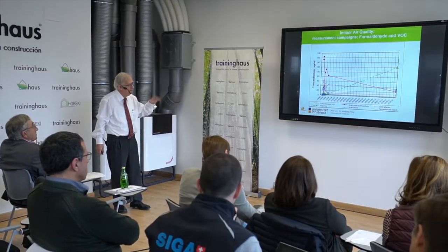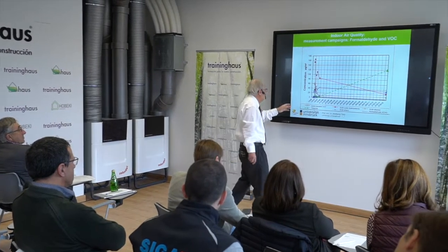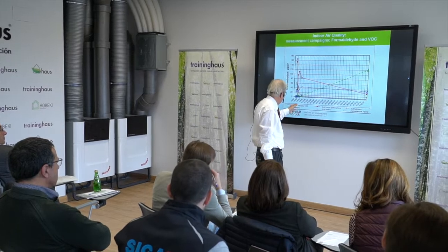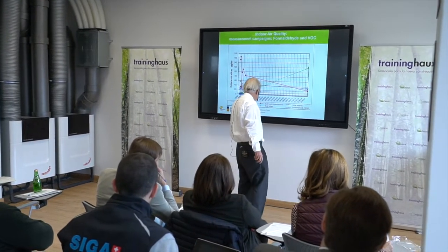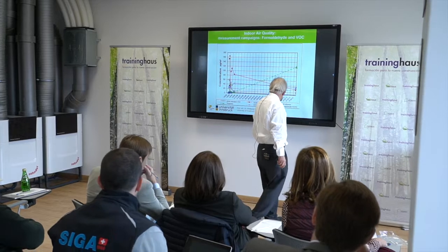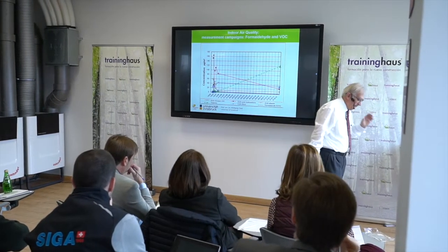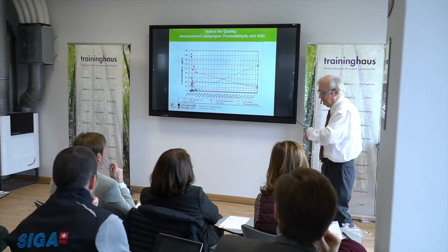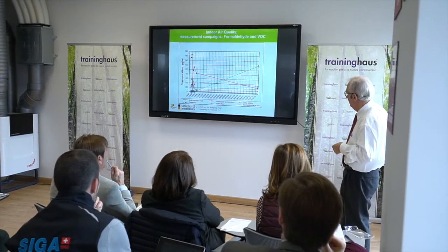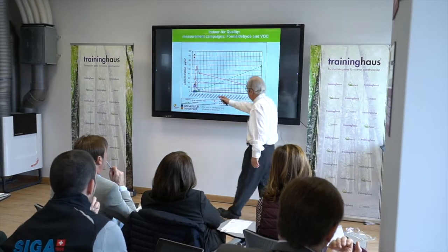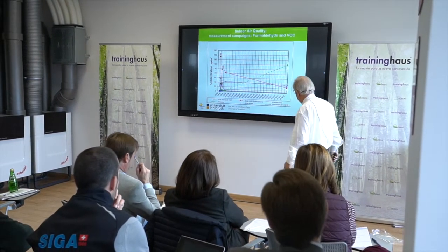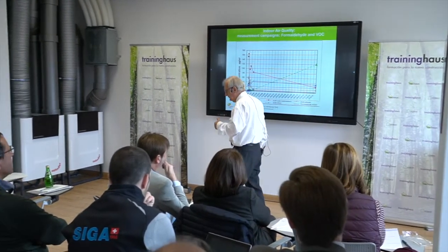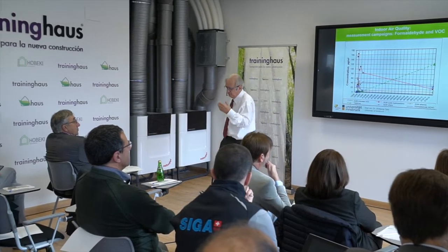It's an interesting thing. We already realized the air quality in the first years where we did the measurement. Indoor air pollutants, we measure a lot of different kinds of indoor air pollution, like VOC, cyclic hydrocarbons, and so on. And we realized that most of those did not come from the construction, they came from the furniture and from other things which were used in the building. And now it's interesting that this changed after the years. So this is a successful path we have gone in German society. Nowadays, old furniture doesn't emit very much, but also the new ones we bring in are now almost free of these kinds of emissions.